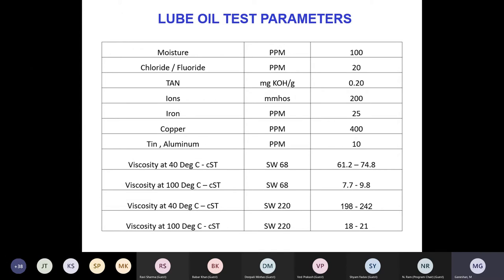Copper had increased, that means it is removing the copper and coming back, depositing somewhere. Tin, aluminium: our bearings are always aluminium based. So that had increased, which means some wear, that means the viscous bearings are getting worn out. So, these are all indications. Same as viscosity, a very important tool, that is where the lubrication quality of the compressor oil is judged.